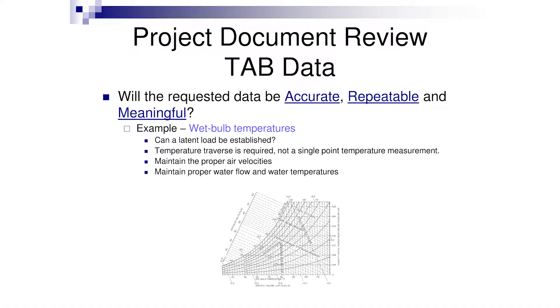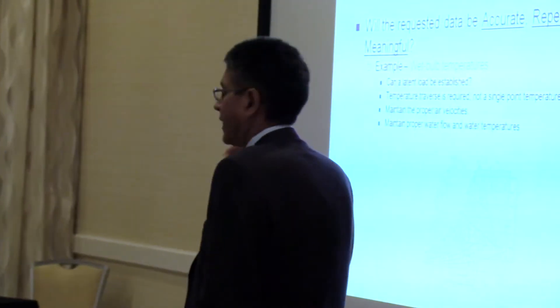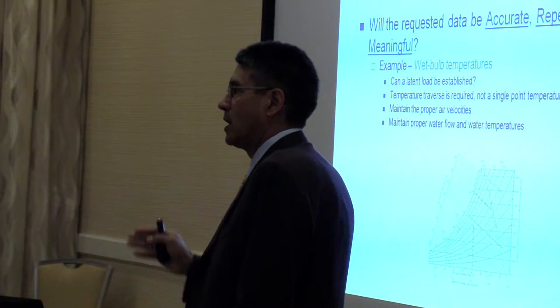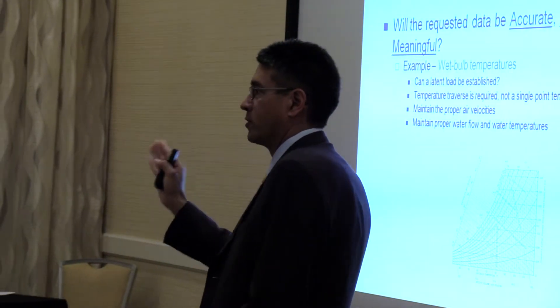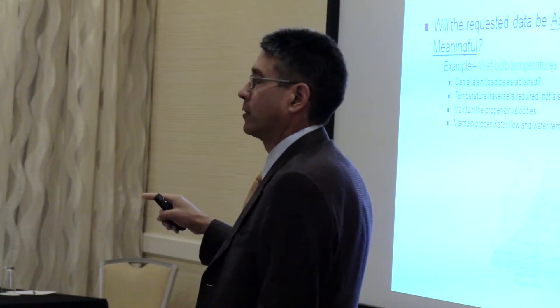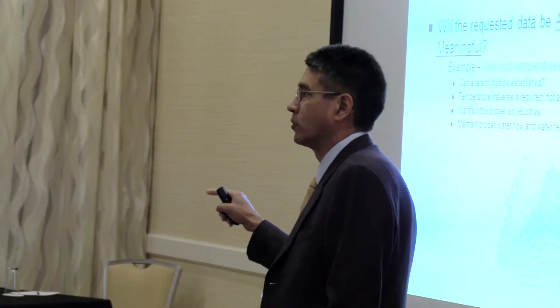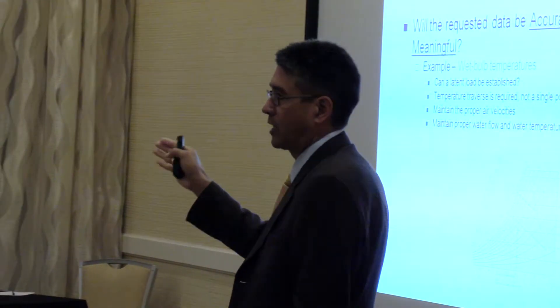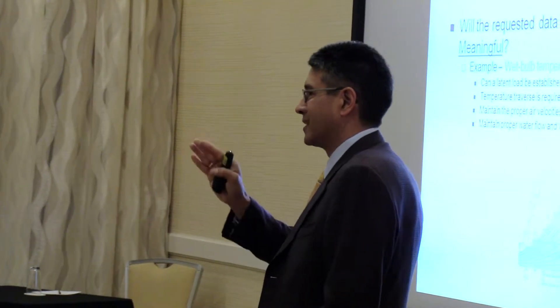When we start thinking about meaningful and accurate data, a good example is wet bulb temperatures. If we need to get wet bulb temperatures off that cooling coil, we have to step back and say: can I establish a latent load on that coil? When I start taking leaving air temperatures and wet bulb temperatures, it needs to make sense and correlate back to the design parameters of the coil. Is the chilled water coming in at steady state — 42 degrees or whatever our design water temperature is?